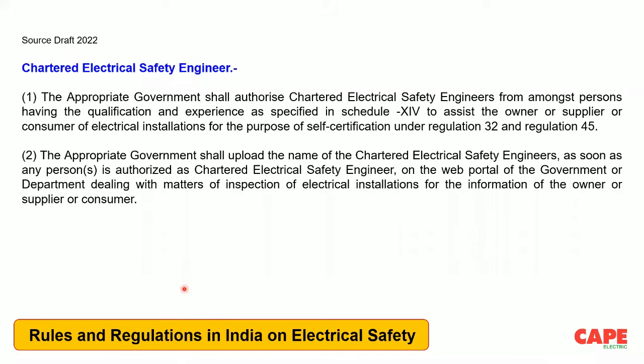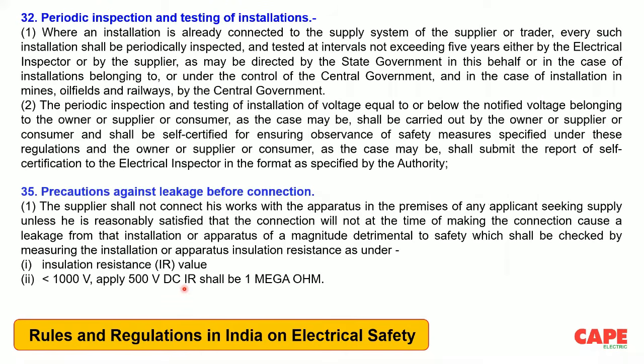Also, the regulation, I think the number is 6, talks about the chartered electrical safety engineer. Who is a chartered electrical safety engineer? What is his qualification criteria and what kind of formats does he have to follow? For example, what kind of test does he have to do? He has to do tests as per regulation 32, periodic inspection, and periodic inspection means every 5 years you have to do the testing which is prescribed as per this particular regulation.